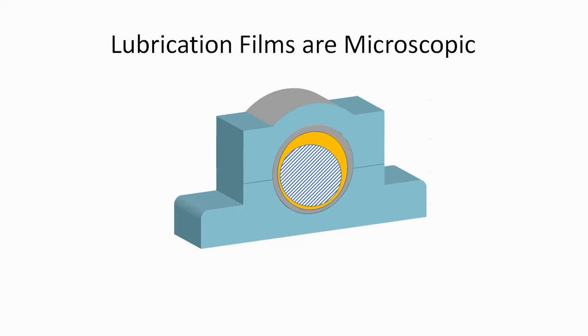In the industry, especially gas and oil and power generation, we want to keep our machinery working as long as possible, and on the other hand, reduce the time and cost related with maintenance. Frequently, premature failure is related with wear and other issues related in some way or another with the lubrication system. The performance of the lubrication system is related with the high velocity oil flushing during the commissioning. A poor high velocity oil flushing will compromise the operation time of the machine.